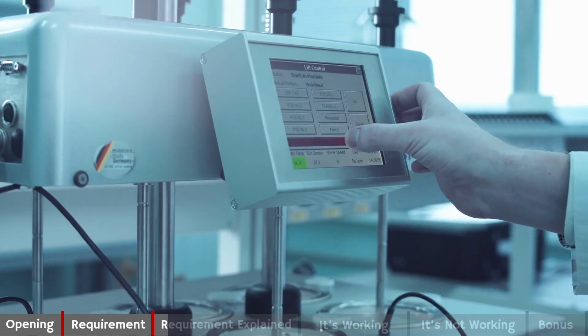Each manufacturer will have processes within their quality management system that have to be validated. Those processes may be water systems, sterilization processes, pieces of equipment like packaging and labeling equipment. It may be standalone software, a water system, or a sterilization system. All of these processes have to be reviewed to determine whether process validation is required.